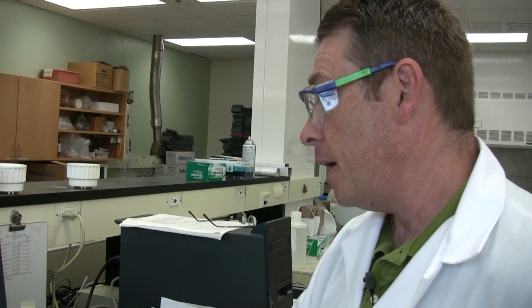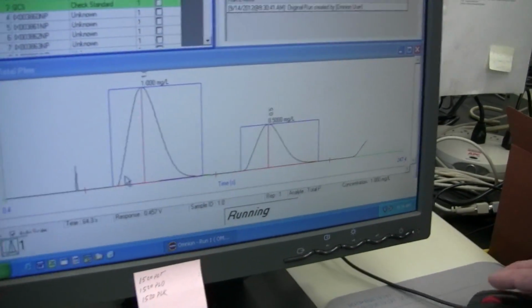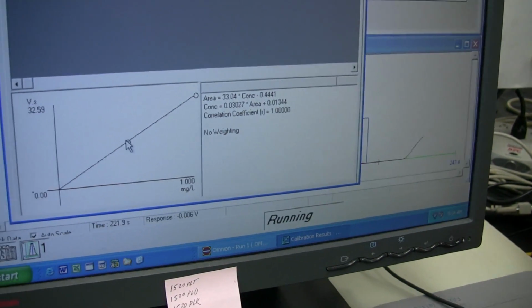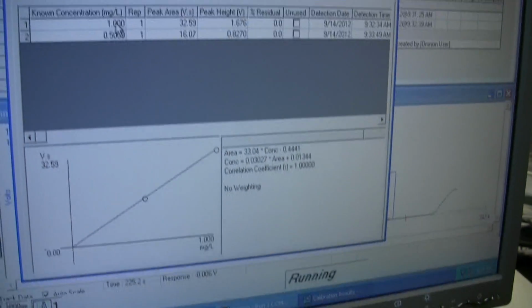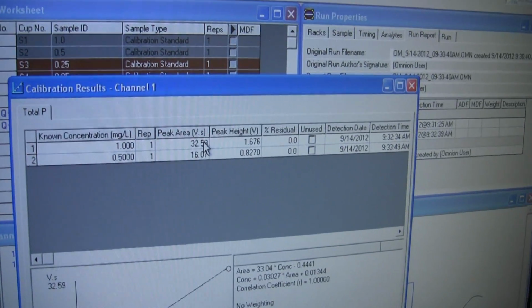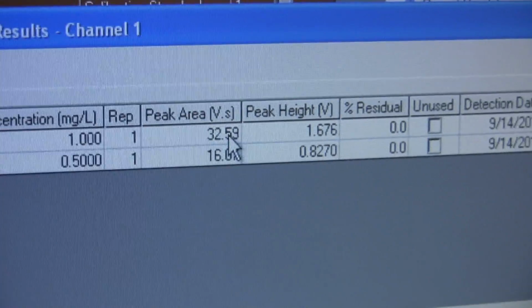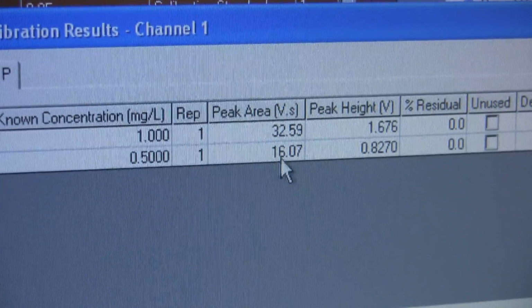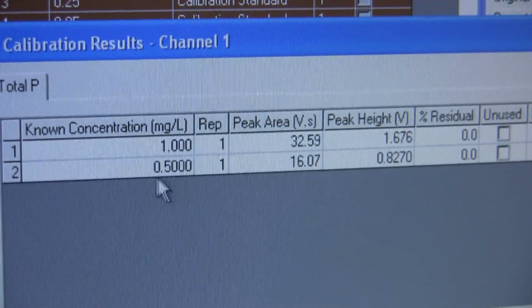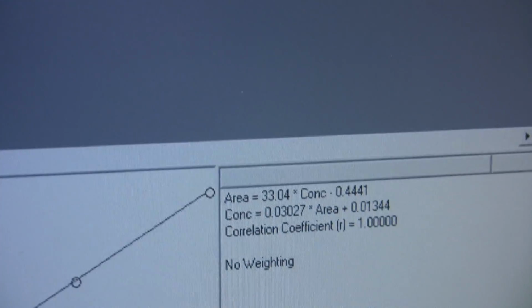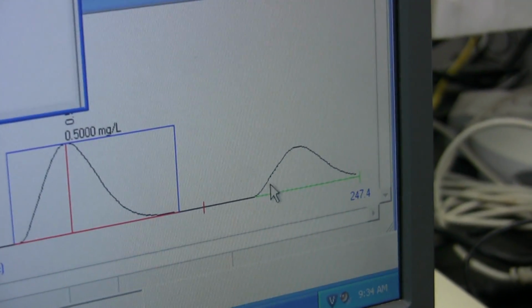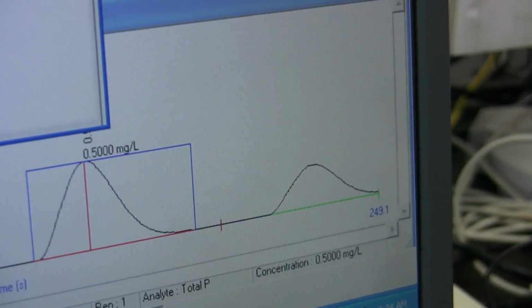Otherwise, we just have to sit here and wait for a bit until the calibration curve goes through, passes everything, and then we can start looking at unknown samples. So right now, we're running our 6 standards to establish our curve. Right now, there's only 2 points plotted. Here we can see our known concentration of 1. The instrument plots peak area as volt seconds. So it says the first one's 32, the next one's 16 something, and a little bit here, 0.25 should be coming out, which is actually coming through right now. So in half a minute or so, it should plot that point, and we should see it appear.